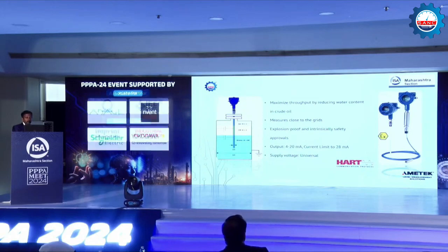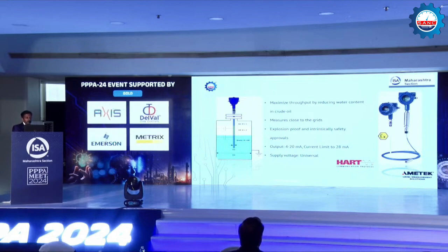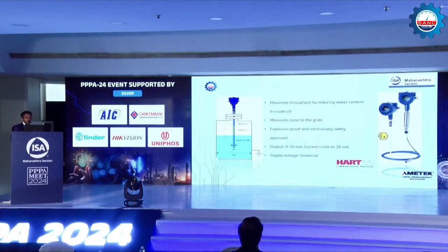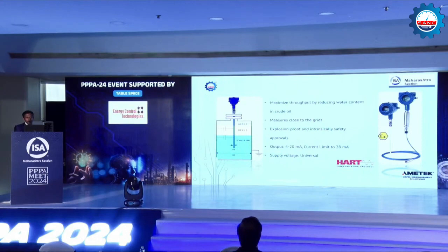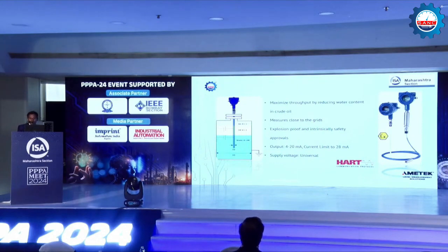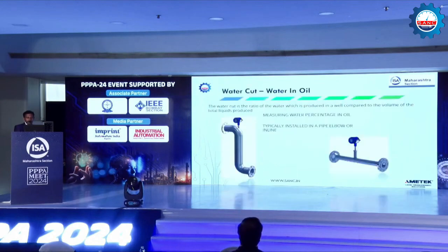Whereas in RF admittance, water is conductive in nature, we call it the aqueous phase, and oil is the insulating phase. So RF admittance measures only the aqueous phase. We always measure only the water after calibration. That is why we are very successful in interface level measurements in desalters. Our product has all the approvals like ATEX and PESO, and it comes with HART protocol, 4 to 20 milliamps, for high temperature and high pressure ratings.